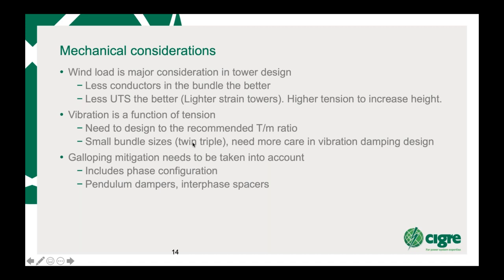You can actually get them, but it's sometimes better to use Stockbridge dampers on either end and then use spacers rather than spacer dampers. But you need quite a bit of care if you're looking at small bundle sizes, which would help your wind load. The other thing you need to take into account, of course, is galloping.